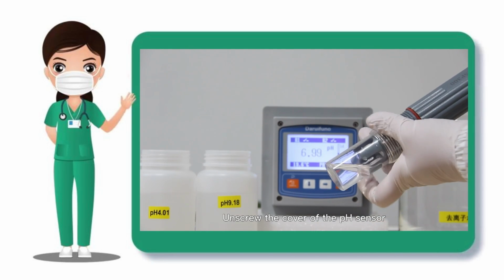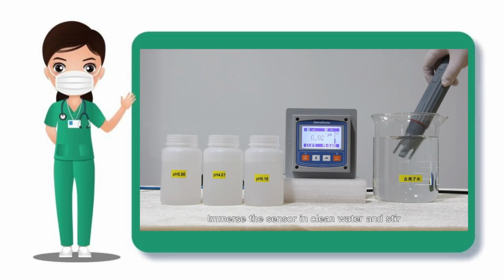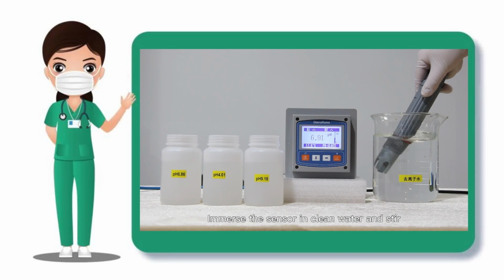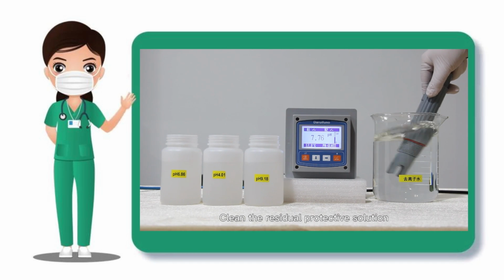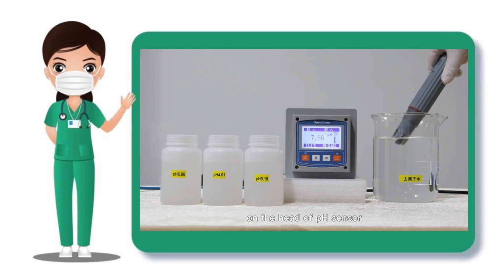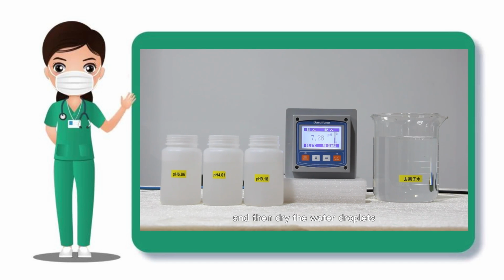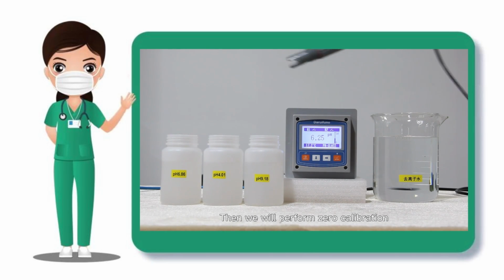unscrew the cover of the pH sensor. Immerse the sensor in clean water and stir. Clean the residual protective solution on the head of the pH sensor. Take out the sensor, and then dry the water droplets on the surface of the sensor bowl, to prevent the residual liquid from polluting the calibration solution. Then we will perform zero calibration.